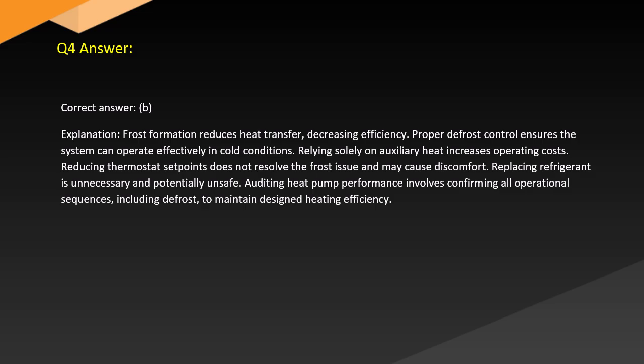Answer. Correct answer: B. Explanation. Frost formation reduces heat transfer, decreasing efficiency. Proper defrost control ensures the system can operate effectively in cold conditions. Relying solely on auxiliary heat increases operating costs. Reducing thermostat set points does not resolve the frost issue and may cause discomfort. Replacing refrigerant is unnecessary and potentially unsafe. Auditing heat pump performance involves confirming all operational sequences, including defrost, to maintain designed heating efficiency.